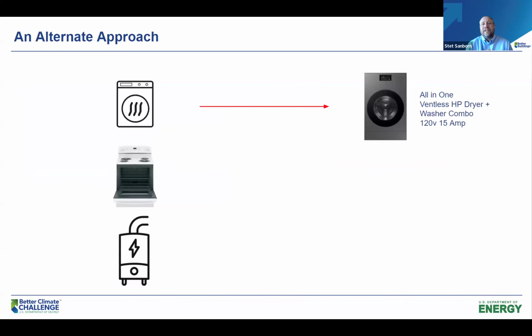So first off, that electric dryer, that is a beast. Electric resistance in any form is a huge power draw, and that alone is going to tip up most apartment panels above their rated capacity. So one of the things that we're seeing introduced in the market within the last year and a half are heat pump dryers. So you've heard of the old school electric condensing dryers where your clothes came out and they were like slightly dry. Heat pump dryers are amazing. I have one in my own house.